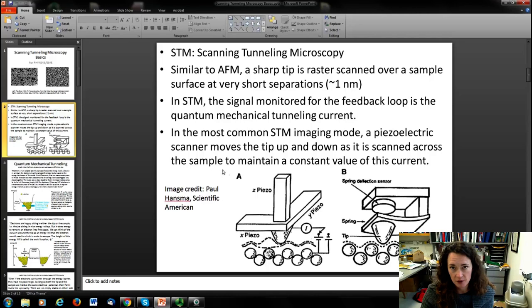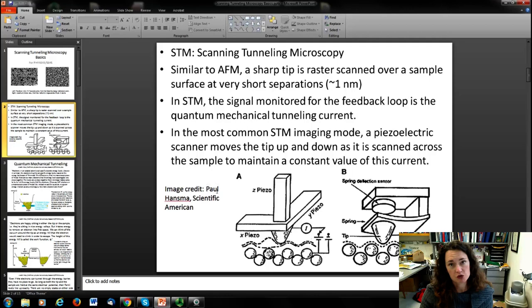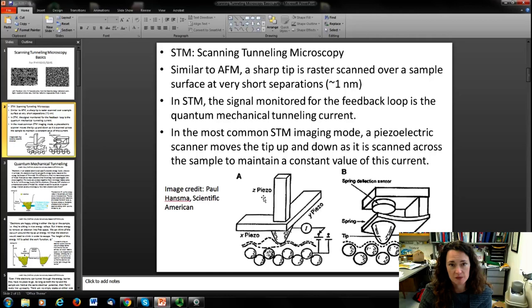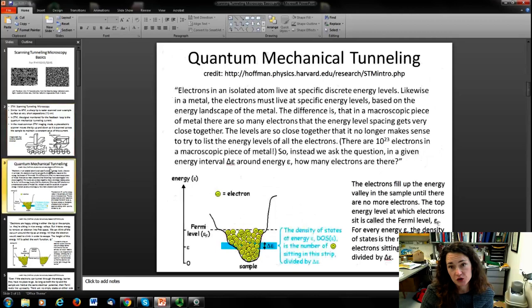Now in AFM, you're monitoring a different signal for the feedback loop than in STM. In STM, the signal that you're monitoring for that feedback loop is your quantum mechanical tunneling current, which we'll discuss more in just a second. In the most common STM imaging mode, it's a piezoelectric scanner that's moving the tip up and down in response to trying to maintain that constant current between the tip and the sample. And oftentimes, though not always, this maps the sample's morphology, giving you atomic scale resolution.